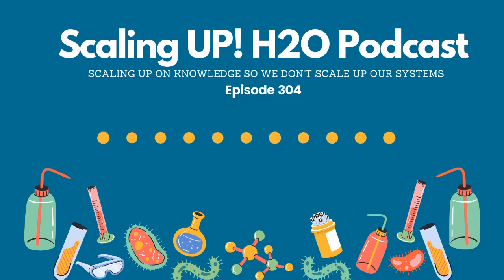I will urge each and every water treater out there that if you are not using corrosion coupons, to please consider to start using that, because again, the only way you are going to know that a problem is coming is once a problem is there. There's no proactivity if you're not periodically looking at what your corrosion rates are.